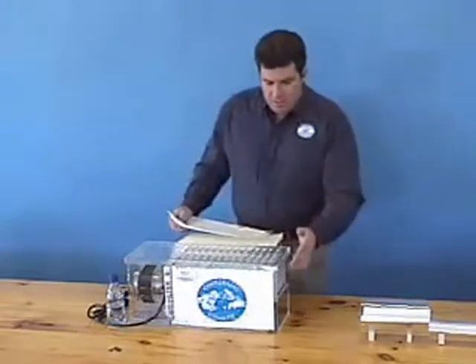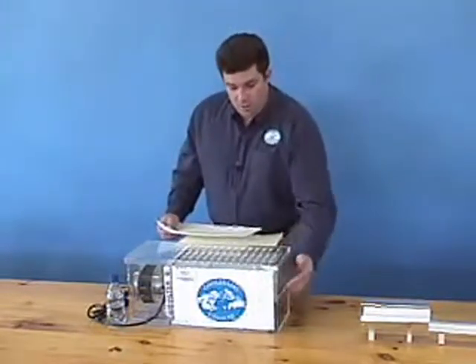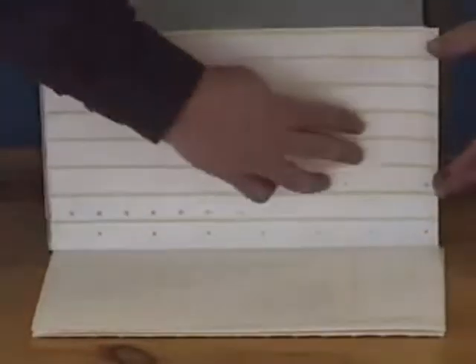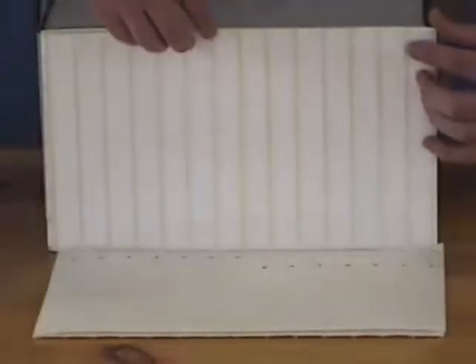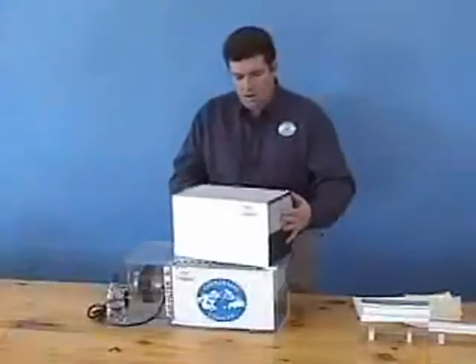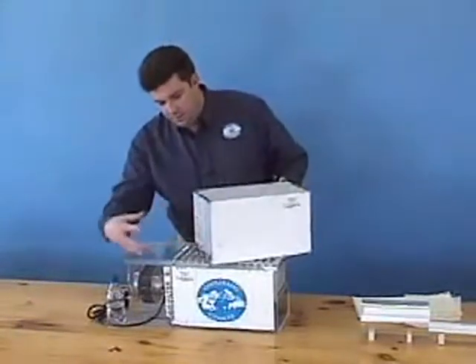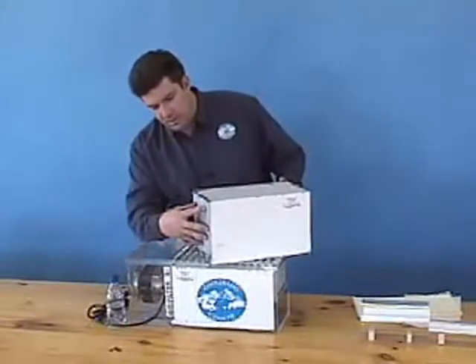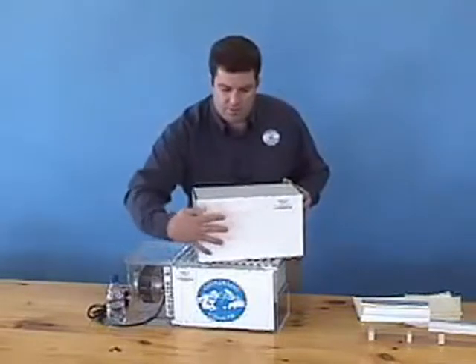Let's take a look at the Coolerado heat and mass exchangers that we use in our demonstration cooler. The plate heat exchangers are made from the same plastic-coated paper that I showed you earlier. We attach guides to these plates to create channels for air to flow through. We then assemble these plates together to create a heat and mass exchanger. All of the air being pushed by the fan enters this end of the heat and mass exchanger and begins to flow in this direction.